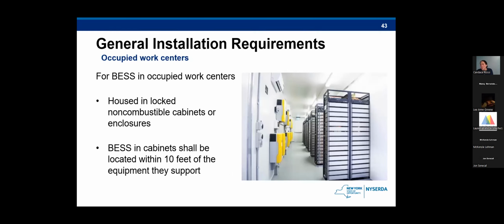Next, we have requirements for systems that are located in occupied work centers. You need to ensure that they are locked in non-combustible cabinets or enclosures to prevent unauthorized access. Additionally, they must be placed within 10 feet of the equipment that they support. So basically, if you're installing energy storage indoors at a school or office building, you just want to make sure they're locked in non-combustible cabinets or enclosures and located near the specific equipment they're supporting.